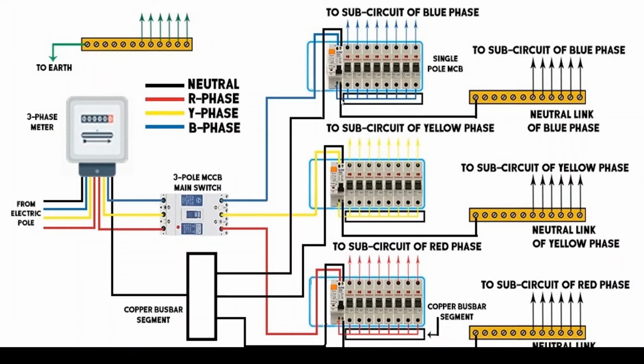Then, as we said, downstream are these breakers, the MCBs. As you see here, the isolator feeds the ELCB connected to all these MCBs, and these MCBs give power to all these downstream circuits. The neutral will be connected here, then it will be connected to the ELCBs, as you can see here. And the earth connections will be given to the circuits directly here. They will not pass through any breaker.